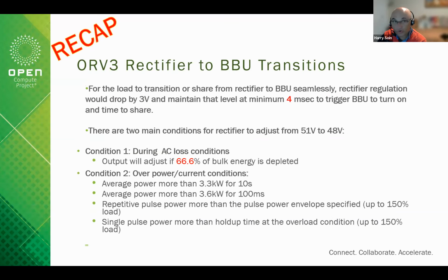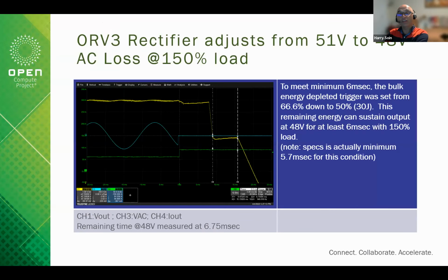Before I get into those details, I just want to show the real measurements of the units. As you see here, there's a transition to meet a minimum of 6 milliseconds as the bulk energy depletes. The trigger was set down, and like I mentioned, we're talking more about energy. It's 30 joules that AE is designing to, and the spec, I believe, is 27. So we just wanted to have more margin.